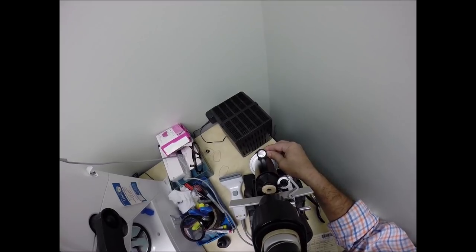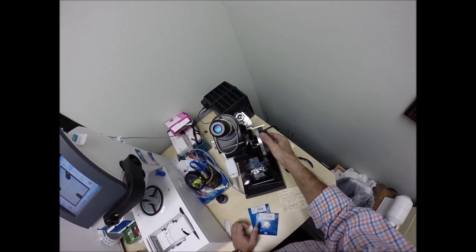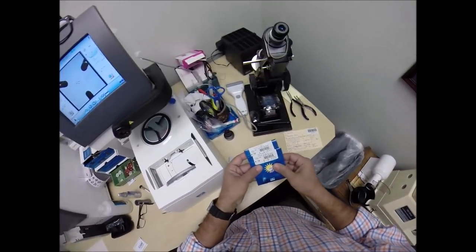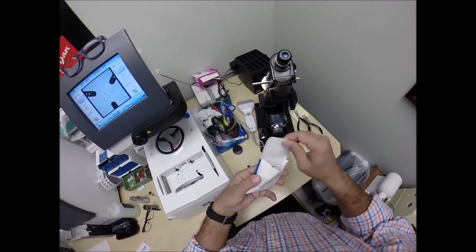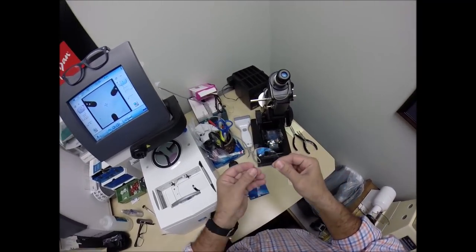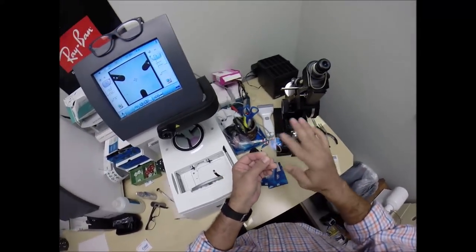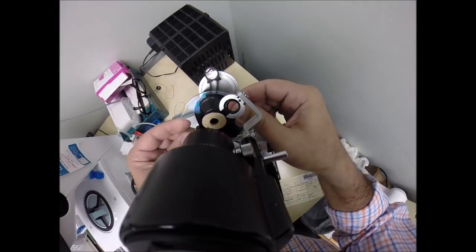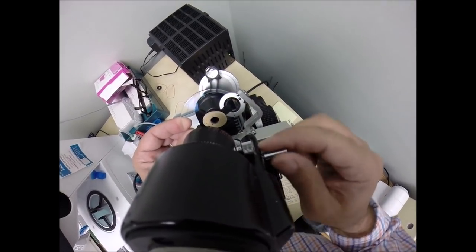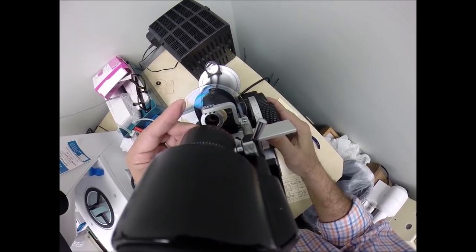Let's put the axis wheel at 126. Put the power drum on minus 1. Then find the minus 1, minus 50. There it is, the one on top. I had a 50-50 chance of getting it right. Take it out of the protective packet. Comes with a laminate on the front of the lens to protect the lens during shipping so nothing rubs against the front surface of the lens. Put it in there. Rotate into the spherical component. The minus 1 component of your prescription comes into view. Check your astigmatism correction. That lines up well.